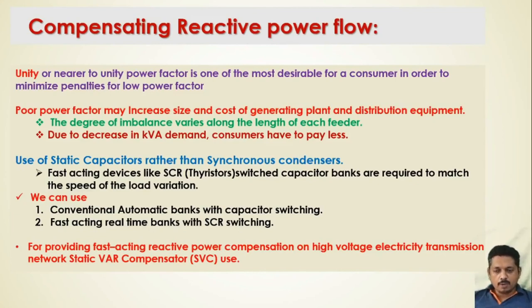Also, if your industry is working on low power factor, that will create an impact on the generating plant, as the size of the generating plant and distribution equipment increases, the cost also increases, and it will depend on the consumers. If we compensate the reactive power for our own organization, then you can also control the KVA demand. That means you pay less electricity bill if you achieve this.